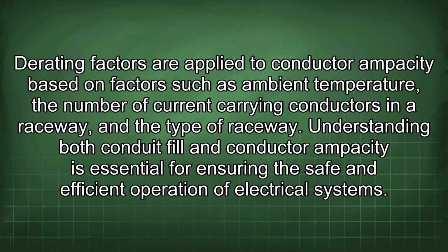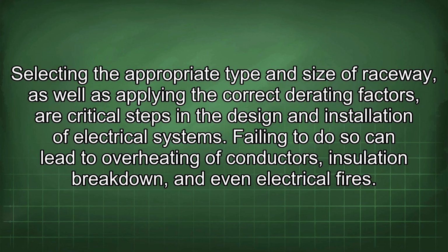Derating factors are applied to conductor ampacity based on factors such as ambient temperature, the number of current-carrying conductors in a raceway, and the type of raceway. Understanding both conduit fill and conductor ampacity is essential for ensuring the safe and efficient operation of electrical systems. Selecting the appropriate type and size of raceway, as well as applying the correct derating factors, are critical steps in the design and installation of electrical systems. Failing to do so can lead to overheating of conductors, insulation breakdown, and even electrical fires.